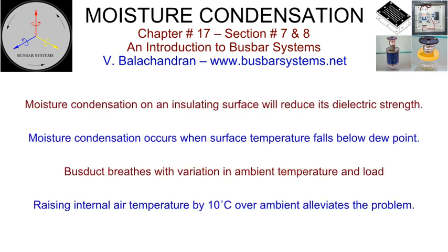When a metal enclosed air-insulated bus has been de-energized during routine maintenance or shut down, condensation can occur due to the variation in the atmospheric temperature. Such a situation can arise even when the metal enclosed air-insulated bus are lightly loaded.